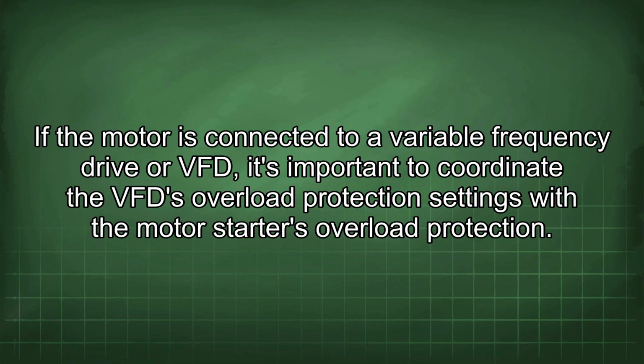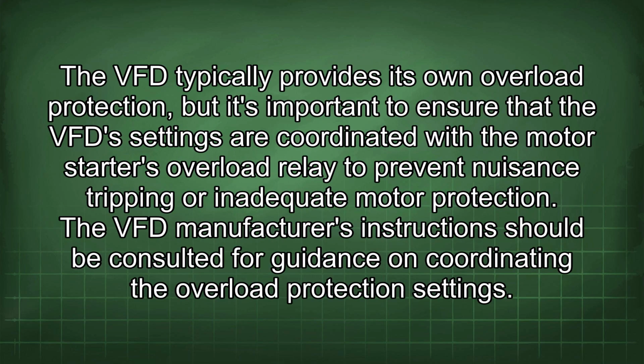If the motor is connected to a variable frequency drive, or VFD, it's important to coordinate the VFD overload protection settings with the motor starter's overload protection. The VFD typically provides its own overload protection, but it's important to ensure that the VFD settings are coordinated with the motor starter's overload relay to prevent nuisance tripping or inadequate motor protection. The VFD manufacturer's instructions should be consulted for guidance on coordinating the overload protection settings.